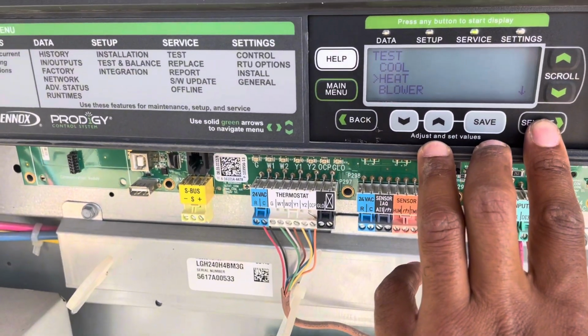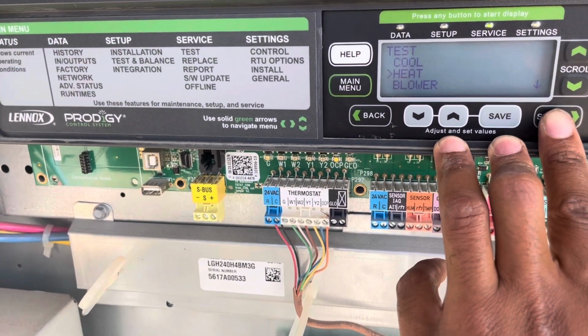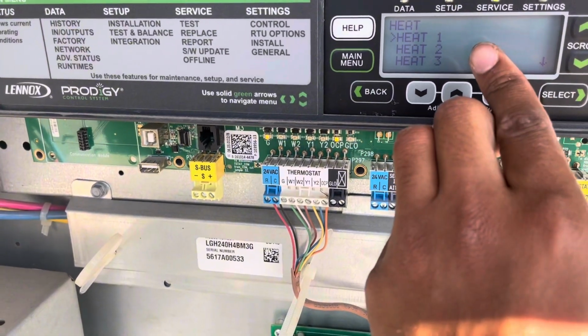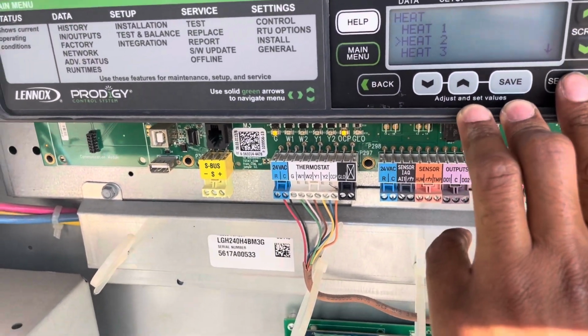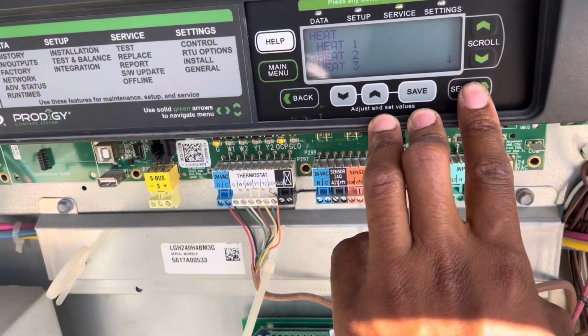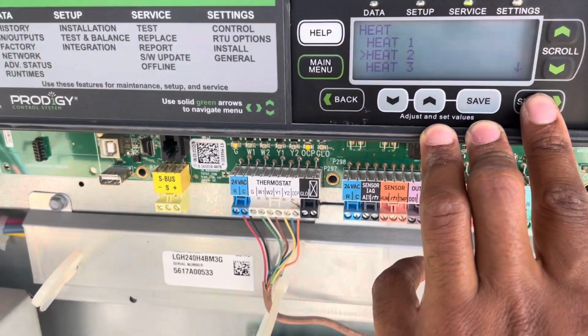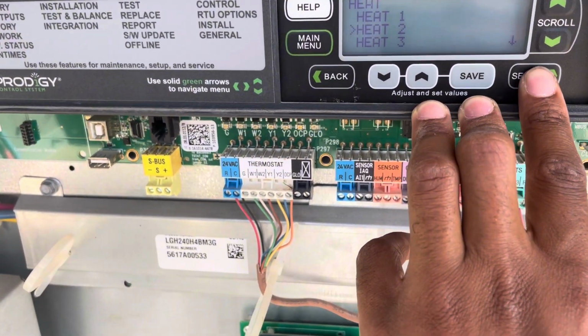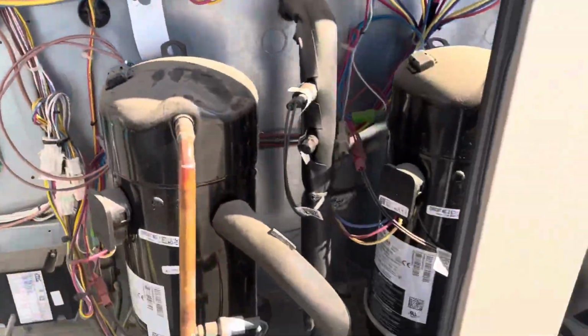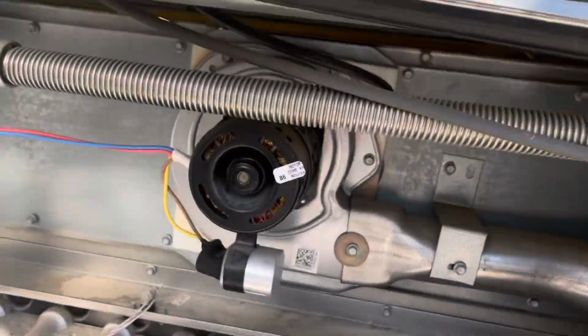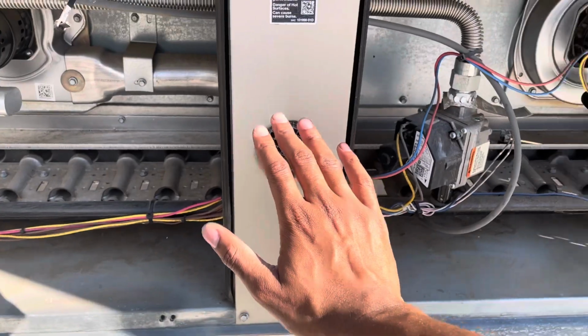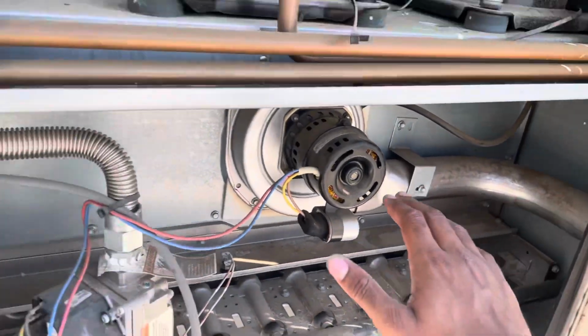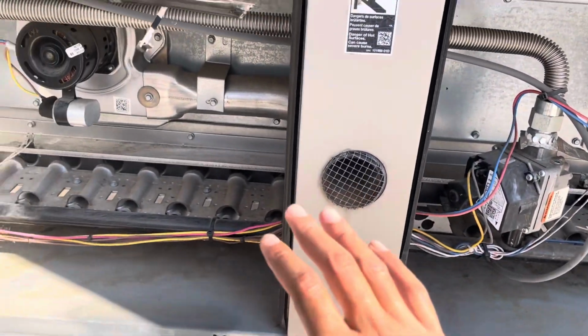So you come down here to heat, select heat. All right, we have 2 stages. So I'm gonna select heat. And the first thing that should happen is the inducer motors should kick on. There we go. Inducer motors are on. Both of them, they sound good. They don't sound like the bearings are shot.